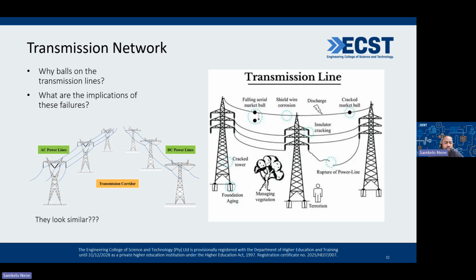We did touch on the break-even point. Normally AC is recommended since it's cheaper to run over long distances when you compare the components. For AC, the major component is transformers. For DC, it's converters, which fulfill sort of the same function because with AC you need a transformer to levelize voltage, and with DC you need converters. Converters are way more expensive compared to transformers, but at some point there's that break-even point. Above 600 kilometers is where high voltage DC lines tend to be favorable.